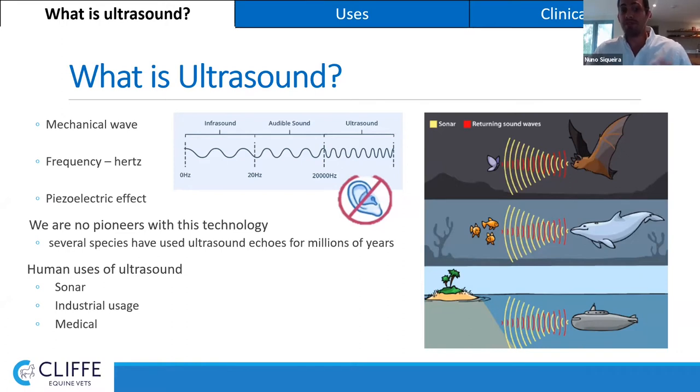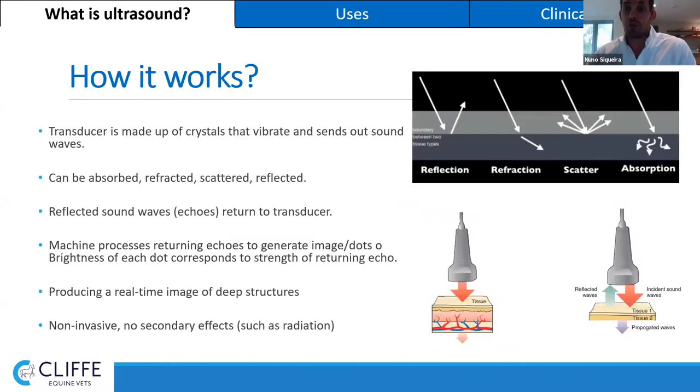We are able to do this because we found out that some crystals have a very interesting property, which is the piezoelectric effect, which means that some crystals, when they have a mechanical stress, produce an electric potential, and the opposite is also true. These same crystals, when they are subjected to electric stimulation, produce a vibration. And this vibration is proportional to the amount of energy that we put on them.